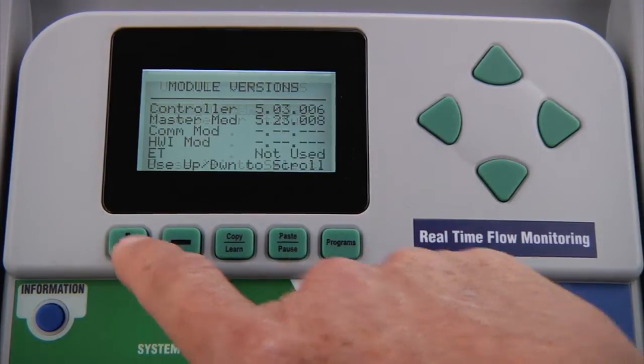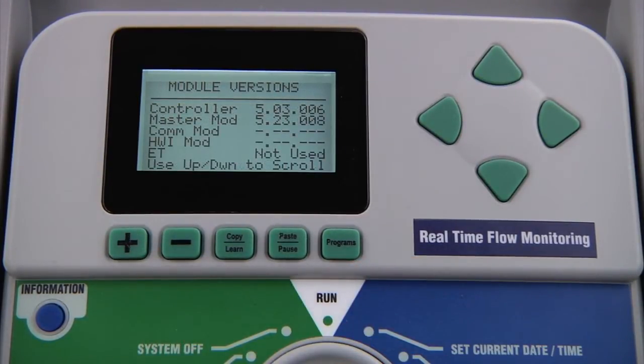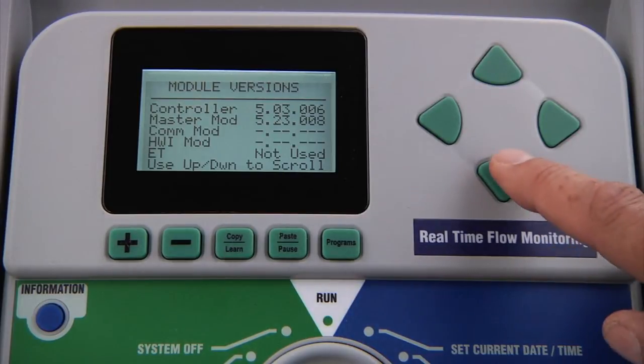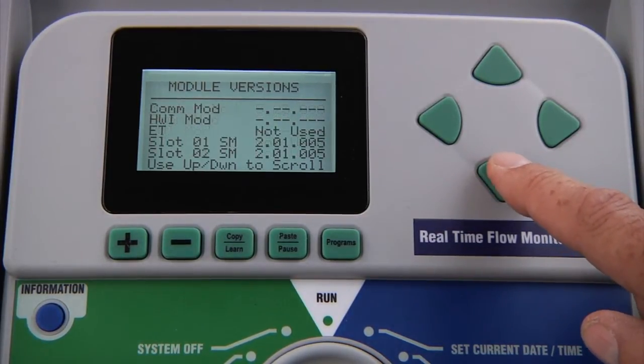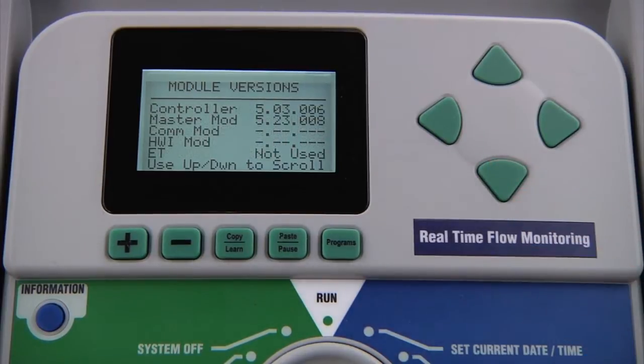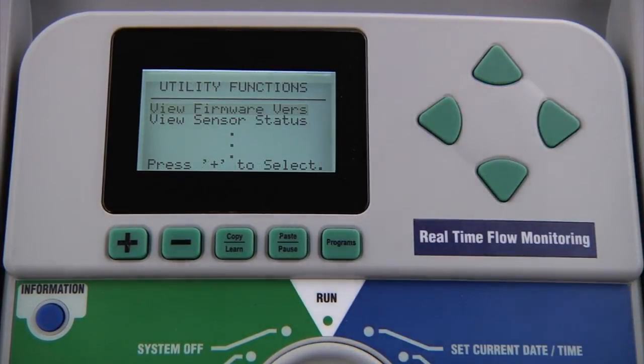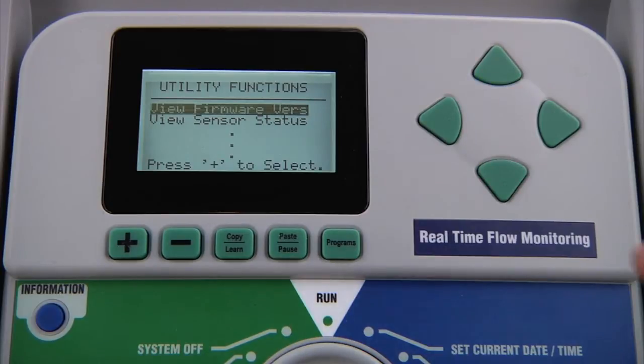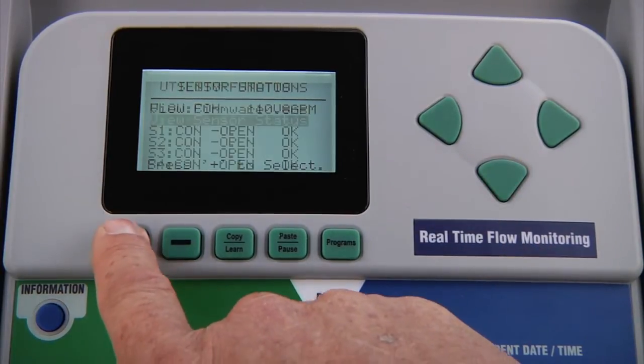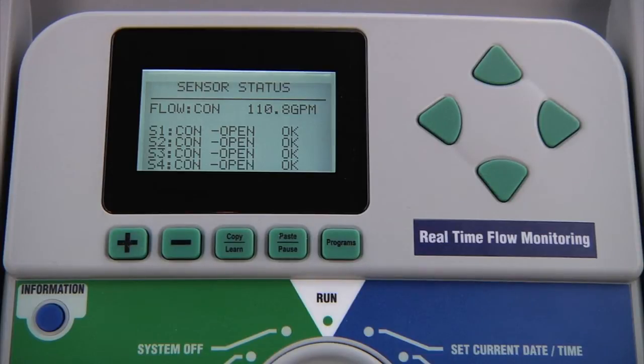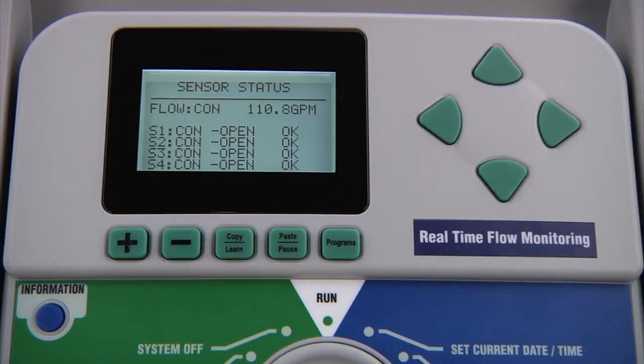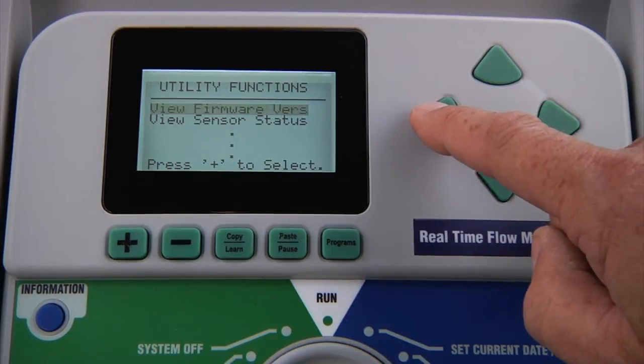Select firmware versions to see the version number of each module in the ACC controller. In a fully loaded controller, you may need to scroll down to show another page with additional modules. In the view sensor status, you'll be able to see if there is a flow sensor attached and how it is attached, whether through the controller or through a decoder. This also shows actual flow in real time. It will also show the click sensors attached to each of the four sensor inputs. To go back to the advanced features main menu, press the back arrow button twice.